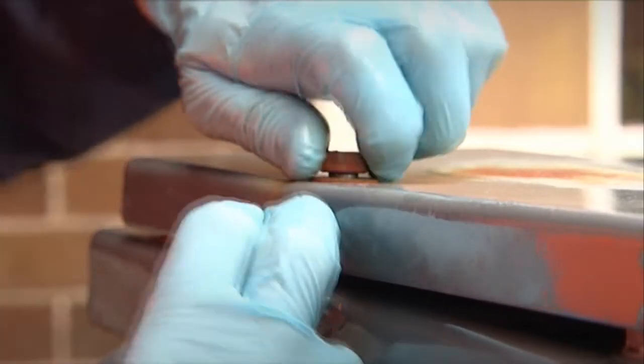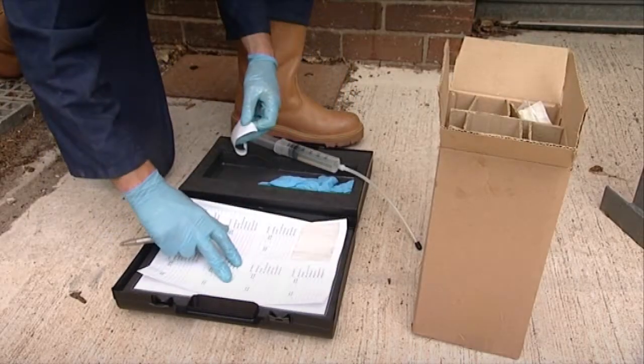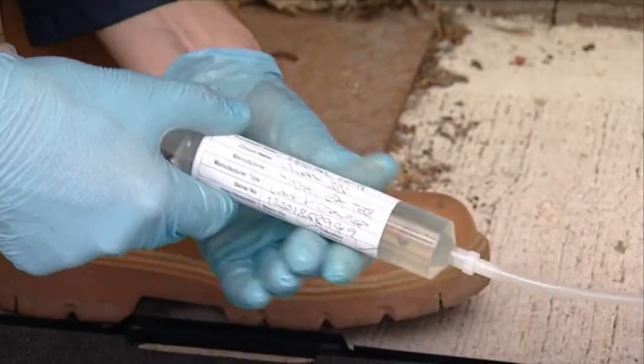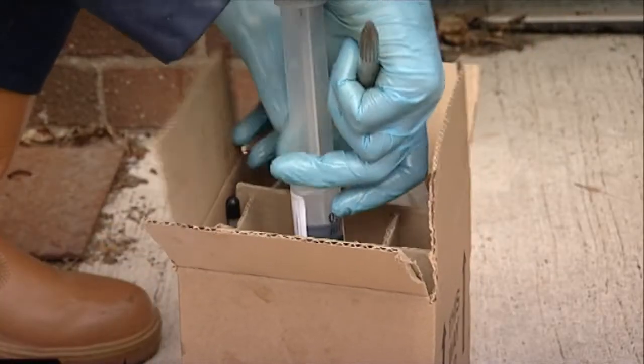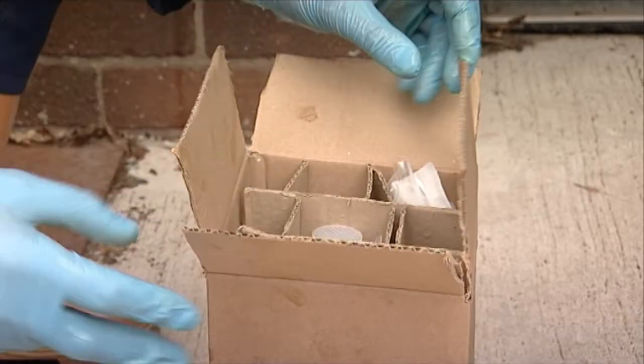Historically, people would use a 500 milliliter sample for oil analysis. Here we are only using 50 milliliters, mainly for a safety reason because we are entering a live tank, but we also determined that you can effectively determine the condition of the oil from that 50 milliliter sample.